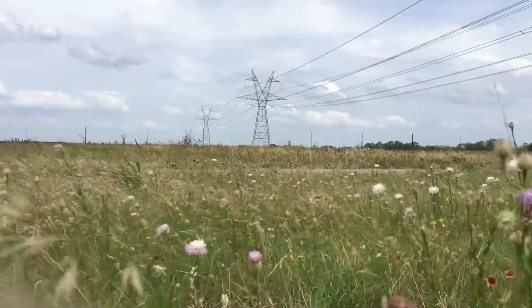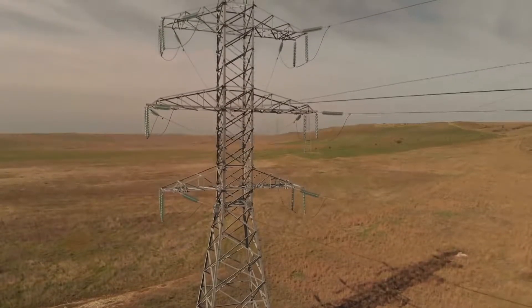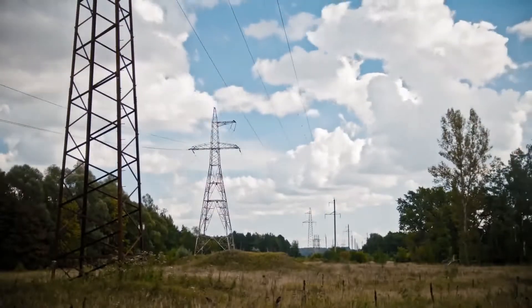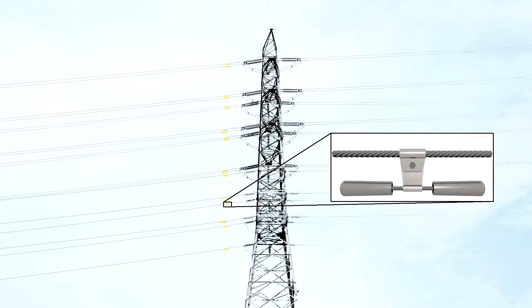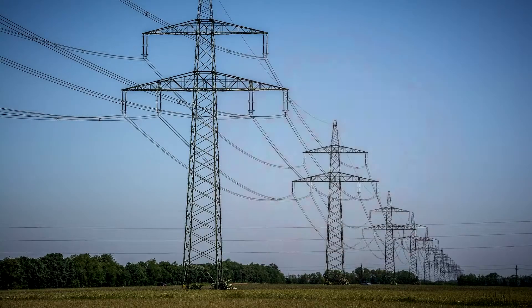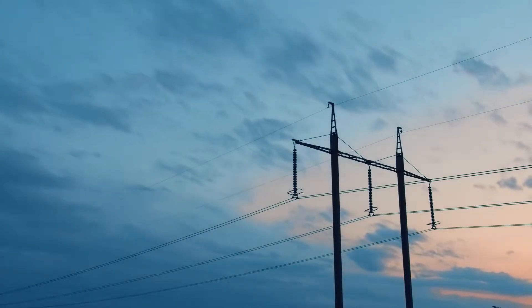High voltage isn't the only challenge associated with electrical transmission lines. Just the selection of the conductors themselves is a careful balancing act between strength, resistance, and other factors. Transmission lines are so long that even a tiny change in the material or size of the conductors can have a major impact on overall cost. Conductors are rated by how much current they can pass for a given rise in temperature. These lines can get really hot and sag during peak electricity demands, which can cause problems if tree branches are too close. Wind can also affect the conductors, causing oscillations that lead to damage or failure — you'll often see small devices called Stockbridge dampers to absorb some of that wind energy. High voltage transmission lines also generate magnetic fields that can induce currents in parallel conductors like fences, and interfere with magnetic devices, so the height of the tower is sometimes set to minimize EMF at the edge of the right-of-way. In certain cases, engineers even need to consider the audible noise of the transmission lines to avoid disturbing nearby residents.